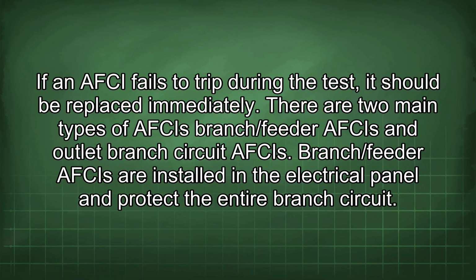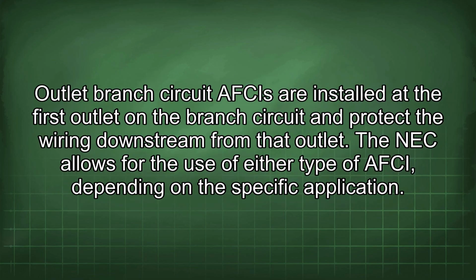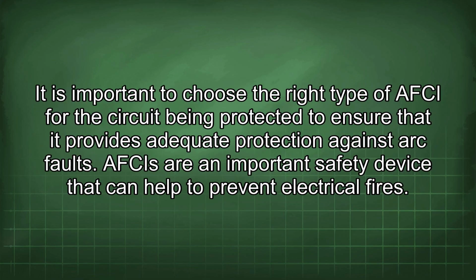There are two main types of AFCIs: branch/feeder AFCIs and outlet branch circuit AFCIs. Branch/feeder AFCIs are installed in the electrical panel and protect the entire branch circuit. Outlet branch circuit AFCIs are installed at the first outlet in the branch circuit and protect the wiring downstream from that outlet. The NEC allows for the use of either type of AFCI depending on the specific application. It is important to choose the right type of AFCI for the circuit being protected to ensure that it provides adequate protection against arc faults.